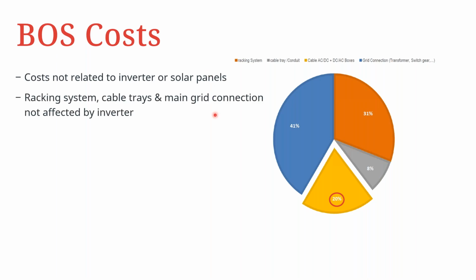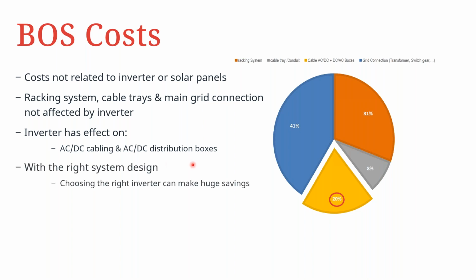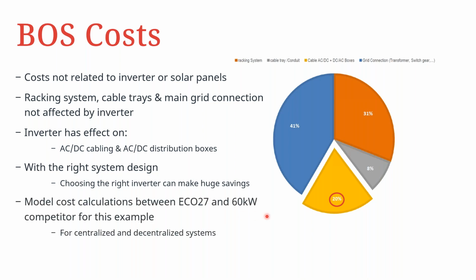So basically we have costs that are not related to the inverter or solar panels. These costs include the racking system, cable trays, and the main grid connection. And then you also now see that the inverter can have an effect on the total cost of the AC/DC cabling, and then of course AC/DC distribution boxes, which you're going to find out eventually. So with the right system design, it is imperative to choose the right inverter so as to make huge savings. And in order to achieve this, we're going to make a model cost calculation between the same ECO27 and the 60 kilowatt competitor for this particular example. We shall be looking at both centralized and decentralized systems.